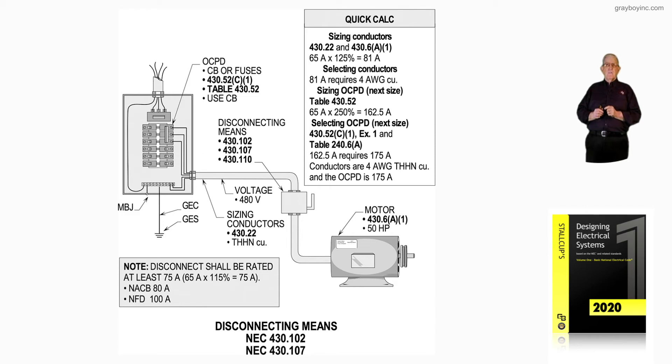250 percent of 65 is 162.5. Decision time. Do I round down or round up? By the 2020 code, you can do whatever you want. I can round it down to 150 or round it up to 175. My choice. But remember, 430.52C1 says round down below the 250 percent. But if I apply exception one to 430.52C1, round up. You can only use exception one when the round down and round up size will not allow the motor to start and run.